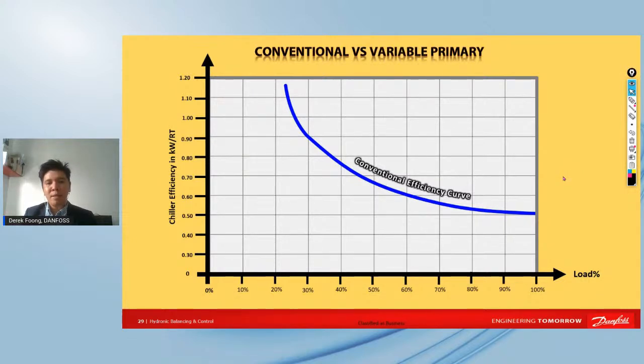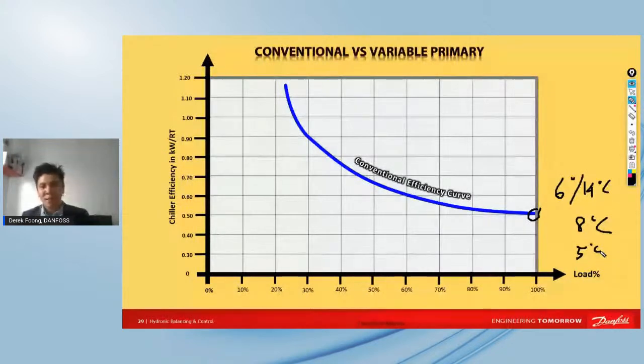Conventional chillers, the typical curve in single centrifugal stage chillers, how they perform is that at full load they are more efficient, right? But at part load, they are less efficient. Now, for this instance, at full load, let's say the set point is about 6 Celsius, 6 to 14. Nowadays, engineers like to have higher delta T, right? So everyone is stretching to about 8 delta, unlike the past decade, when we always saw around 5 delta or 6 design. So I'm very glad to see this.